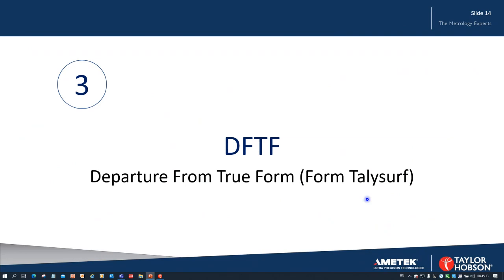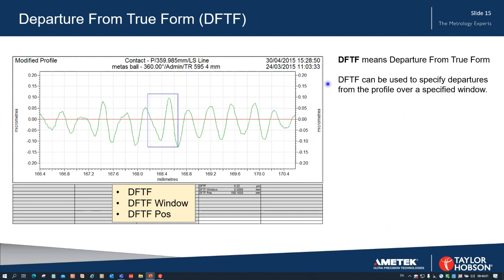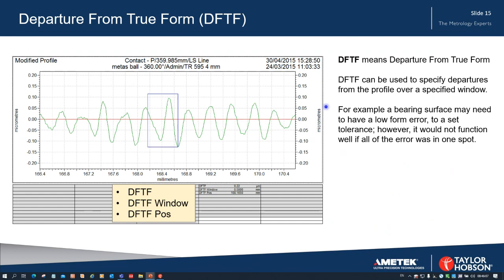Let's have a look now at departure from true form. Previously we looked at an area where leakage may occur circumferentially. If we consider a shaft and a seal, we may find that leakage will also occur along the length of the shaft, so we're interested in form variations along the shaft. We would measure this on a Form Talysurf instrument or on the Talyrond, but in a linear direction rather than circumferentially. DFTF — departure from true form — can be used to specify departures from the profile over a specified window, just as we saw on the roundness profile. A bearing surface may need a low form error to a set tolerance, but again it would not function well if all that error occurred in one spot.